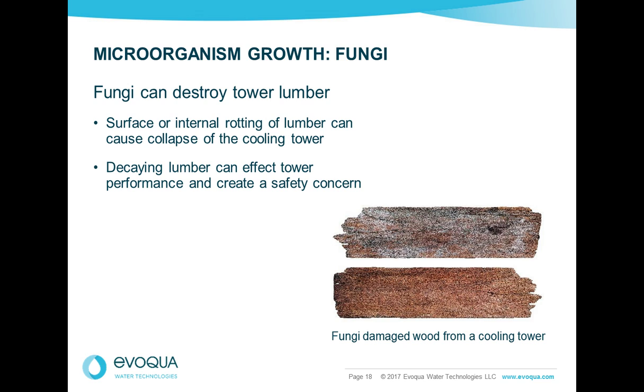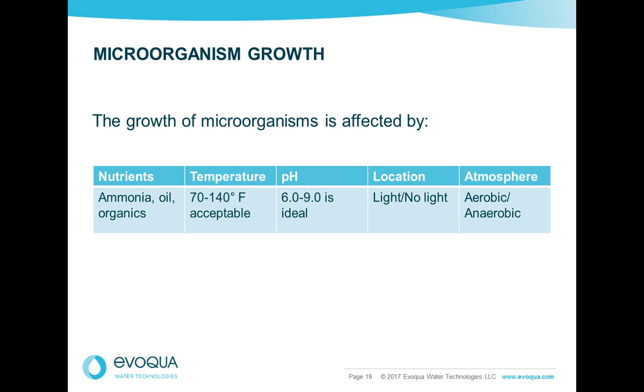Also, as I mentioned earlier, you can have fungi in the system. Fungus can eat cooling tower lumber. So controlling the fungus is important in a lot of cooling systems, most cooling systems. Microbiological growth can be affected by nutrients, ammonia, temperature. You're usually stuck with operating somewhere on the ideal temperature between 70 and 140, which is a good temperature for bacteria. pH 6 to 9 is ideal for bacteria. So they're pretty happy with the pH. Location is usually outside, in the light, in the sunlight. The atmosphere is normally aerobic. You're aerating the water. So the bacteria are very happy there.